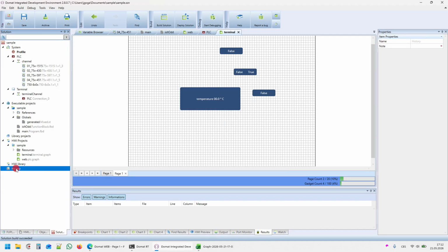So right click, add new history. There can be multiple different histories on the PLC. So we can click on it and turn it on with the check mark here. We have a choice of synchronous or asynchronous. In the first case, you just need to set the storage time period. By default, it's 1 minute. We don't need to fill in any other variables. If we want asynchronous, we also need to map the variables for permission and writing. We can also insert our own timestamp into the historical data.